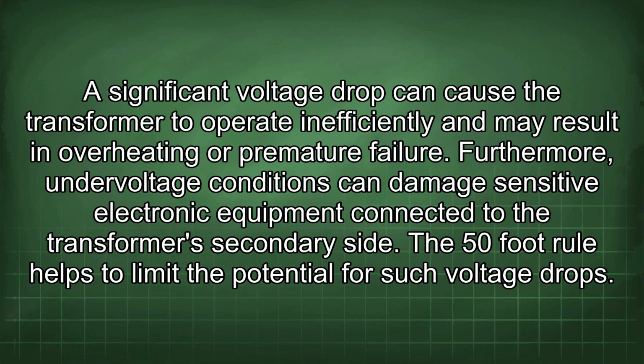A significant voltage drop can cause the transformer to operate inefficiently and may result in overheating or premature failure. Furthermore, undervoltage conditions can damage sensitive electronic equipment connected to the transformer's secondary side. The 50-foot rule helps to limit the potential for such voltage drops.